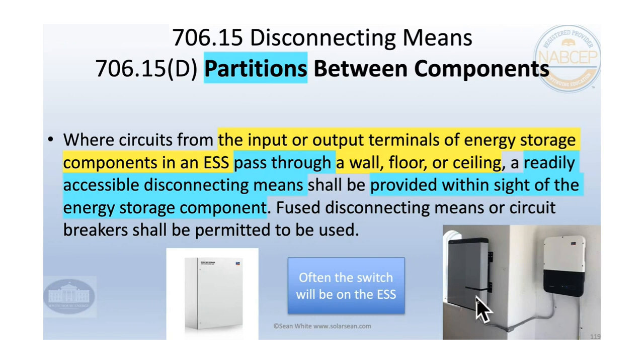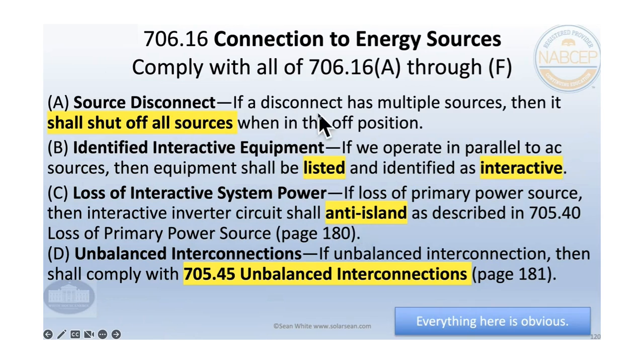There could be an AHJ requirement, or the utility sometimes wants to see things on the DC side, which I really think the utility should focus on the AC side because that's what's going to affect them. And then you can have a DC disconnect over here on this side. So if a disconnect has multiple sources, then it should shut off all sources, not something super common. Maybe you could say this, if you're the SolarEdge StorEdge, you turn off that DC disconnect, it should shut off the battery and the PV. And that would be something in the listing too. So you wouldn't really have to worry too much about that because it's listed that way.